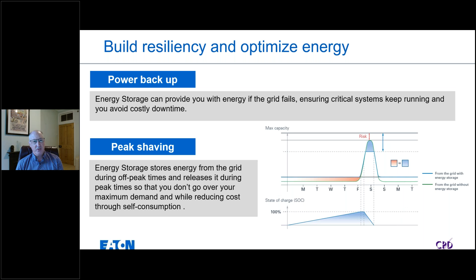I had an example of this on a project recently. It was a large supermarket. They could only get a 250 kVA supply from their local DNO. To get a larger supply required grid reinforcements up to 132,000 volts, and irrespective of the colossal cost of that upgrade, they couldn't do it before 2030 at the earliest. They had a forecast store demand of over 300 kVA, with a 250 kVA grid supply, so battery energy storage was able to mitigate that and provide that additional 50-60 kVA that they needed during their store trading hours. So peak shaving is quite a common application.